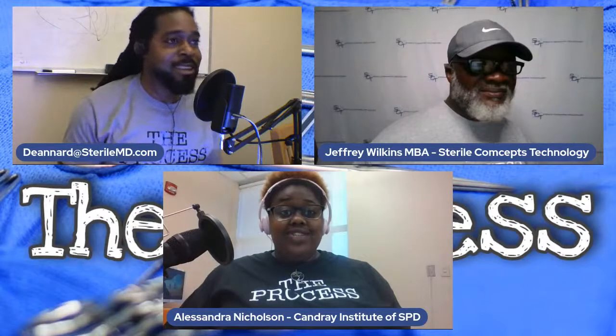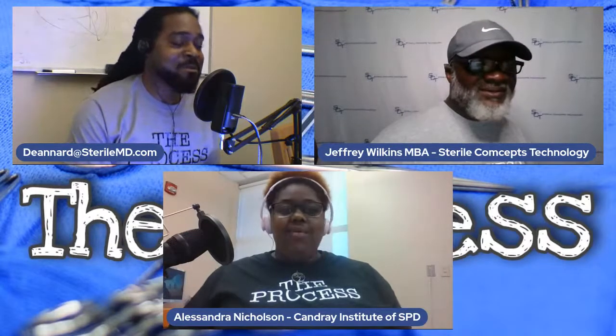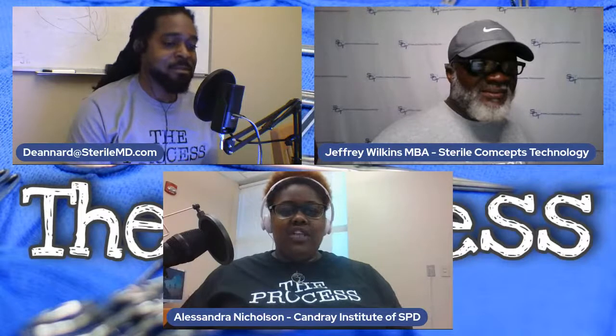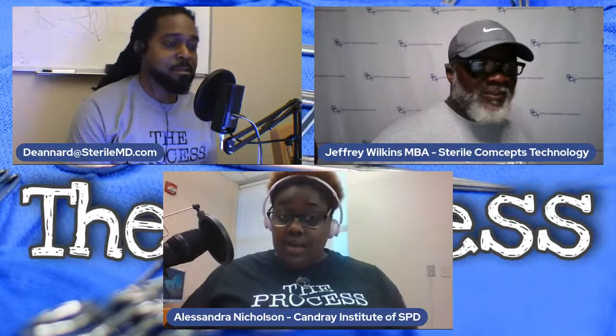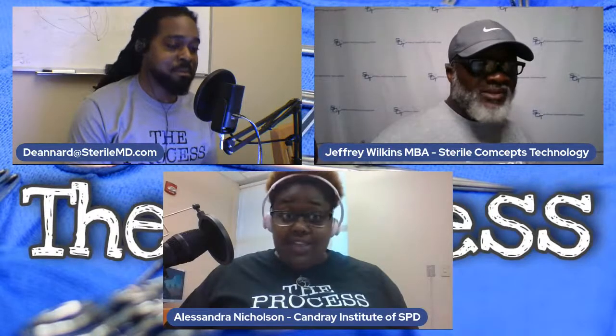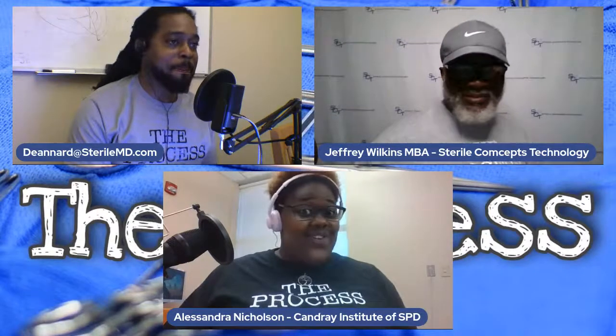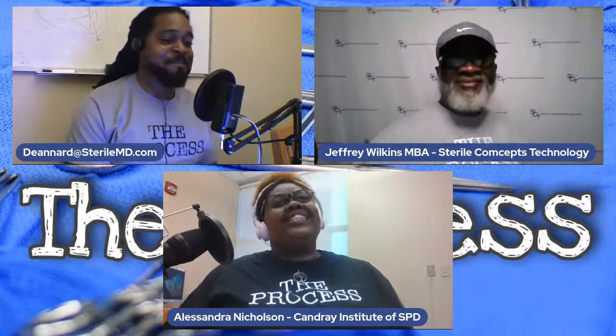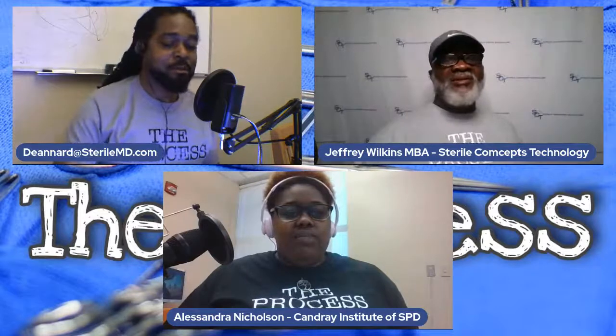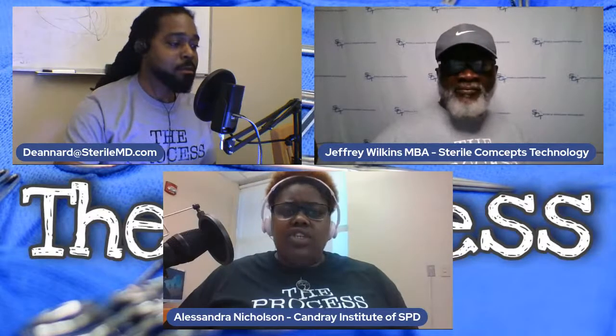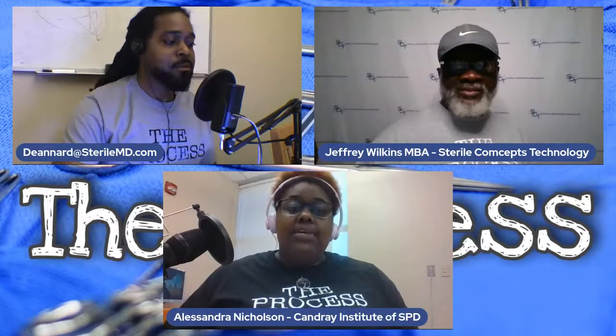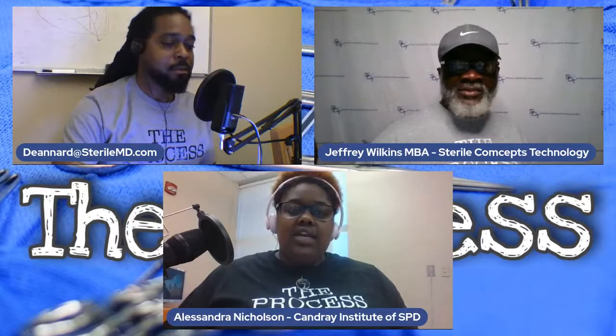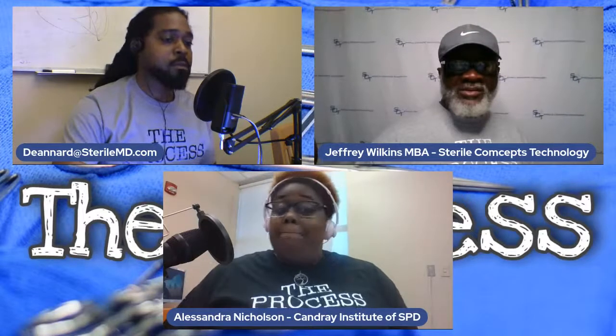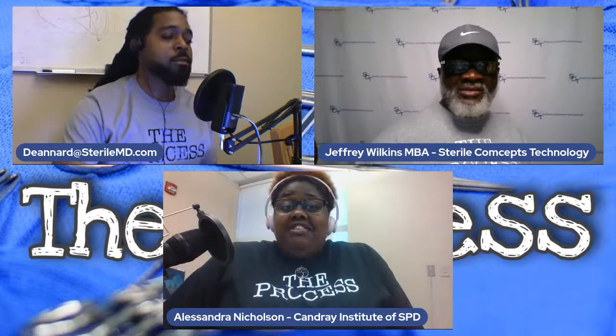Salindra did this to me the other day. I had one a couple months ago with Sharon where she talked about the Da Vinci, and I was like, honey, I never saw that in the IFU. Let me get on the floor right now. But I just saw one from Salindra Bearfield where she posted about the Arthrex shavers, that the handpiece, the handle can actually be dislodged and taken off and cleaned underneath. Been cleaning shavers for 14 years, never heard about it.